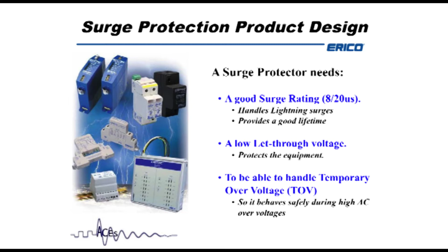The sine wave you can see is just a superimposed overvoltage condition. The little red dots are where that metal oxide varistor's voltage is exceeding its clamping voltage, and it starts to get quite hot, and ultimately it'll catch fire. That's why we put that thermal fusing in.